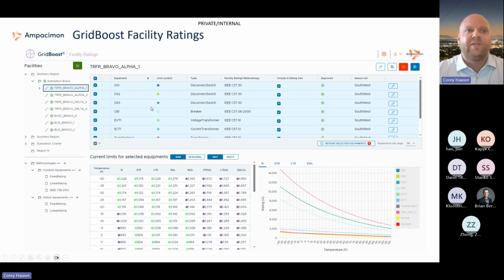It has these limit symbols applied down in the graphical image below, or I should say the table image below, showing the different ratings and which is going to be the most limiting based on those. In terms of the amount of ratings, here you have normal, short-term, long-term, and various others — you can have as many or as few as you want. On the right, it graphs it out, so you're able to graphically see the most limiting piece of equipment. As you scroll through that graph, it'll give you the rating for each piece of equipment included in that graph.